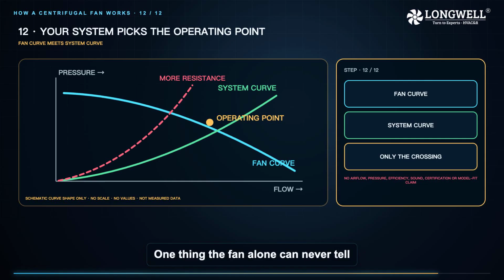One thing the fan alone can never tell you is how much air you will actually get. The fan has a curve, your ductwork has a curve, and the only flow that exists is where the two cross. Change a filter, add a bend, close a damper, and the crossing point moves. That is why a fan which performed perfectly on one job can disappoint on the next, and why a selection is only as good as the duty point you hand over with it.